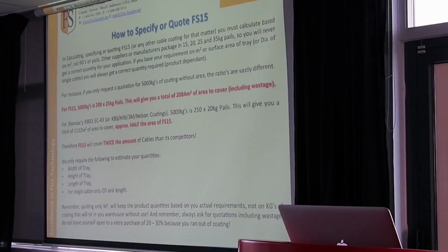So if you base your requirement on metres squared or surface area of tray, or diameter of single cable, you'll always get the correct quantity required. And to break that down, for instance, if we get a request only for a quotation of 5,000 kilograms of coating without area, the ratios are very different. For FS15 or FS11, our cable coatings, 5,000 kilograms is 200 x 25 kilogram pails, and that will give you 2,084 square metres of surface area, including wastage.